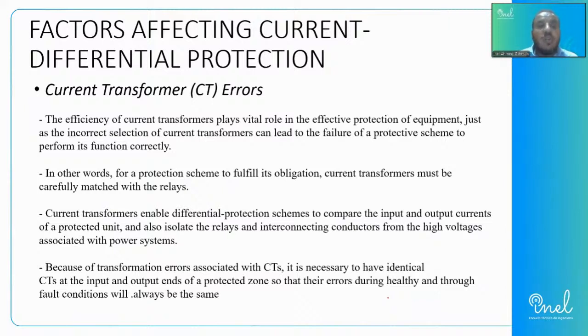So let's focus now on which factors we should take care of, those that affect our differential protection on a transformer. We said that if there is any error in the current transformer, such error may be in the ratio, in the phase shift, or in the alignment. So any type of error in the current transformer will lead to false operation. That's why any transformation error associated with the CT should be identical for both sides, at least to achieve healthy operation during the fault condition. So we should take care of any transformation error that may exist in the current transformer.